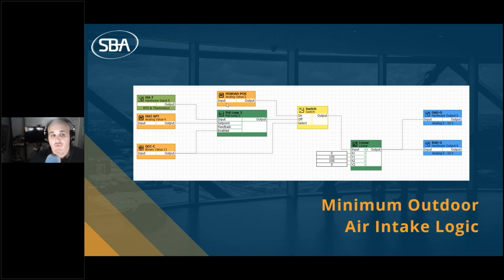The reason you're going to do that is typically we're using economizer to get some free cooling. So we're going to drive to our mixed air temp and our mixed air temp set point with the economizer, and we're going to take the lower of or the higher of the two outputs, right? So a max block. And that will make sure we are always at our minimum outdoor air damper position when we're in occupied. Okay, let's continue along.